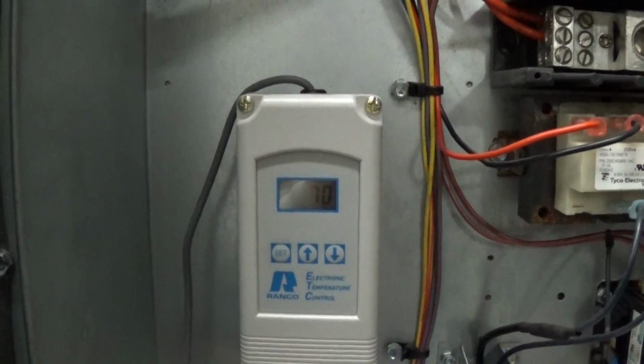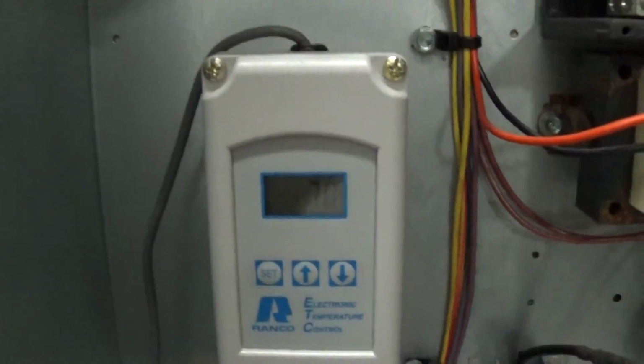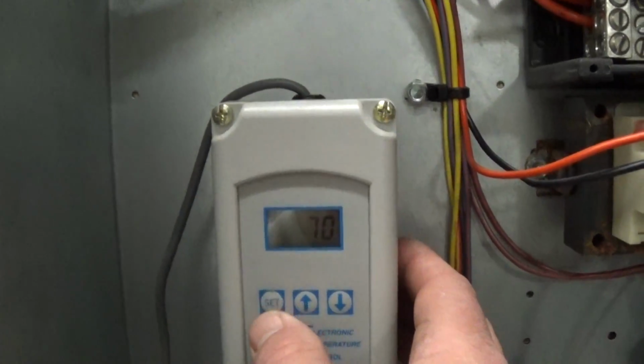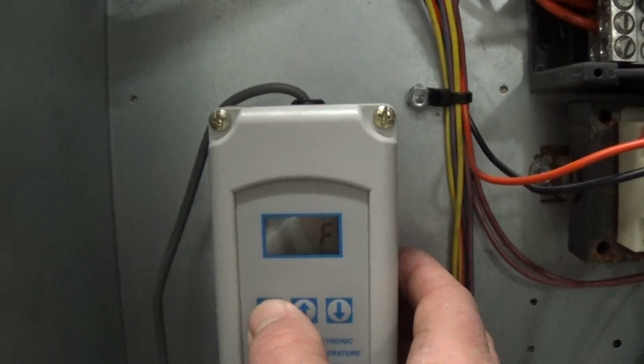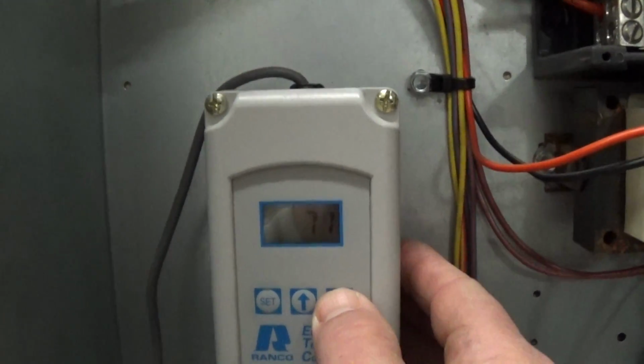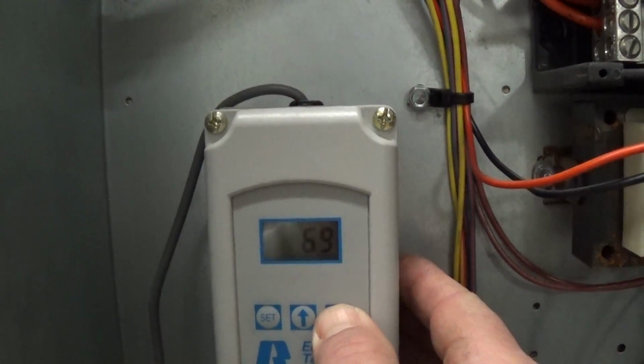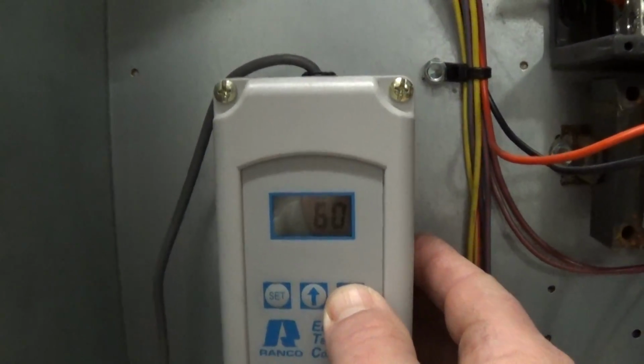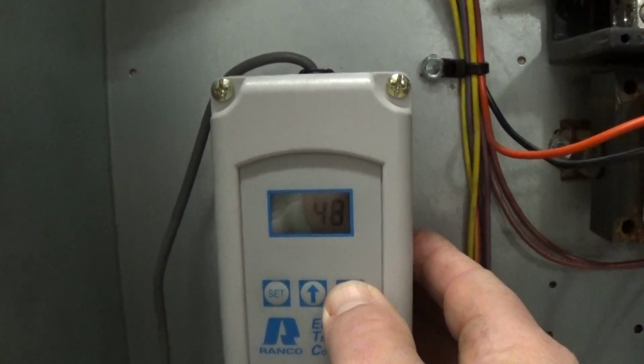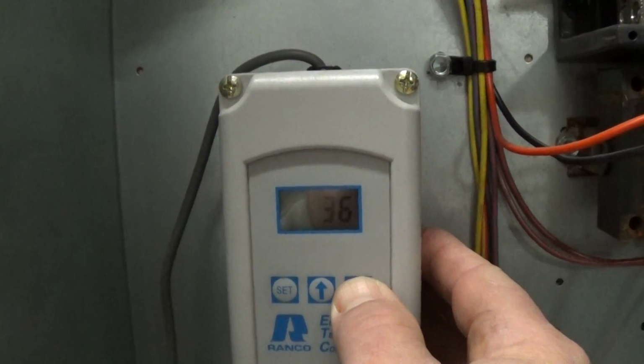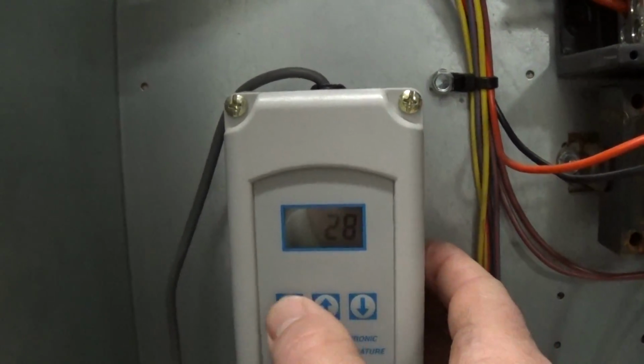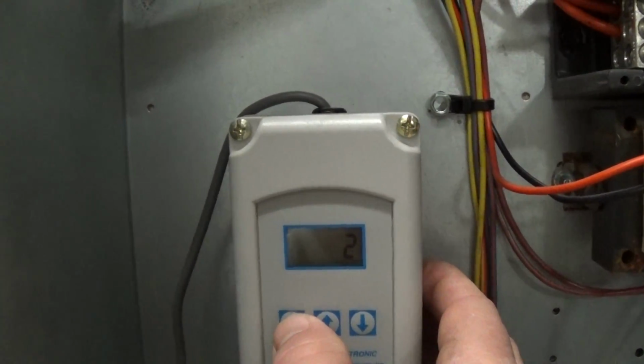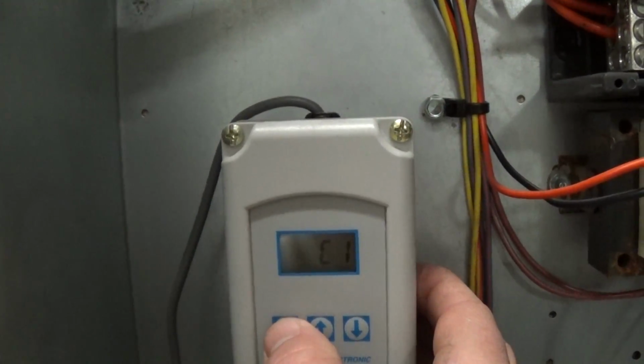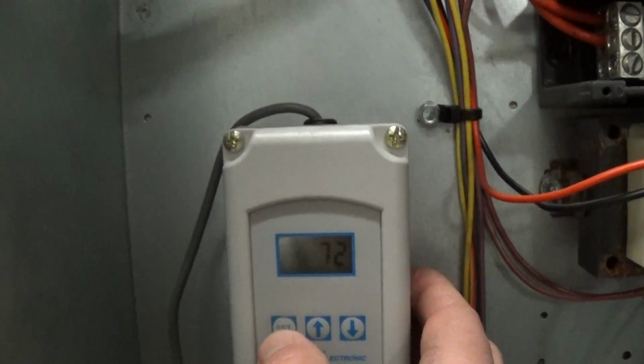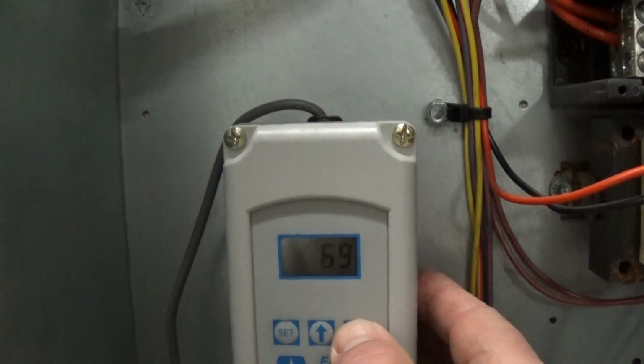I'm going to bring both of them down to actually 28 in this case. So I'm going to press set, Fahrenheit, set. I'm going to bring it down to 28. Set. I'll leave the differential at 2. Set again. I'm in cooling mode 1 confirming. Now I'm going to cooling mode 2. I'm going to bring it also down to 28.